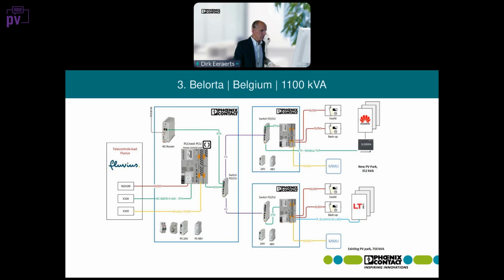If we look at the next example, this plant was built in 2 phases. We have a first phase that was built about 10 years ago, 750 kVA. This is rooftop with local consumption, and the client added a new part to it, and because of this the total capacity exceeded 1 MVA, which was at that time the limit for power control. And so just the addition of this 350 kilowatts caused the DSO to put their telecontrol cabinet on site.